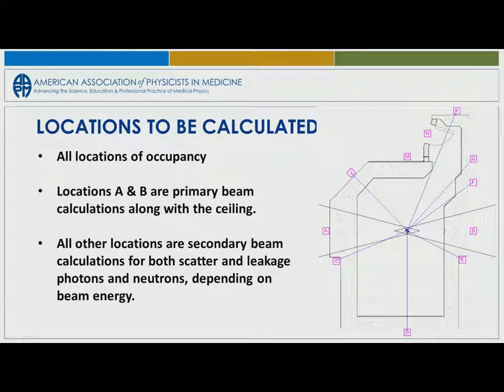So, what are we looking at when we're looking at these locations to be calculated? You really have to look at every place that you could put a body, preferably a live body. But when you have all these locations, we label them simplistically A, B, C, D. Every one of these different places, because like here's your primary barriers, A and B would be your primary barrier points of calculation. All these others are secondary points of calculation. This is a semi-traditional maze vault, but I guess I would call it a very short maze. But this is typical of what you will find. And for all these secondary beam locations, you'll have to calculate it for both scatter and leakage, and then for both photons and neutrons if you've got 10 MV or above. So all that makes life interesting.